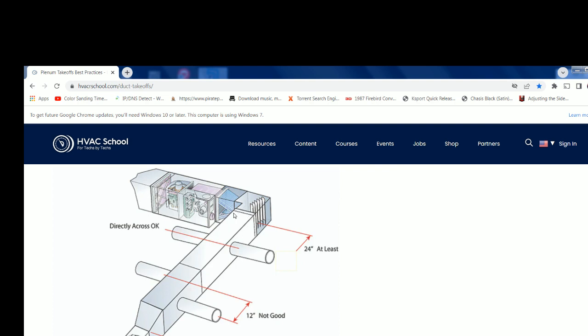And this is for 1,360 square feet. So we got one box. I got my ducts coming off here on both sides, and I actually have one duct coming off the end. Now, you're not supposed to have any ducts off the end. The reason for that is if you blow through a straw, all the air will come out at the end first before it comes out the sides. And this is essentially what happens in the heating duct system. So it's wrong. I have to redo it.